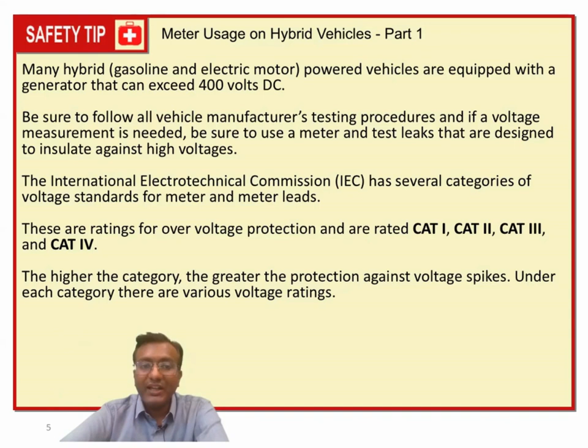There is a standard institute called the International Electrotechnical Commission, IEC, which has made several categories for these multimeters as per their voltage ratings: Cat 1, Cat 2, Cat 3, and Cat 4. Depending on whether the voltage is below or above a particular level, we have to use the corresponding multimeter category.